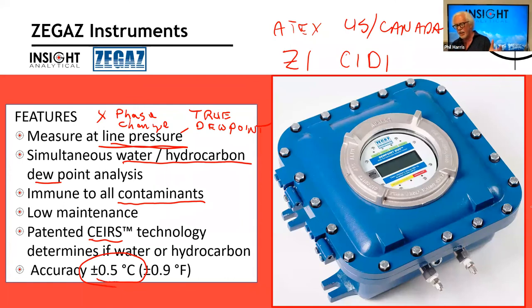Now the analyzer has a cycle too. It's got to cool down the mirror to measure the dew points, and so there's some time delay with that as well. On the analyzer, we'll often see a few minutes of cycle time. Transport time is fairly fast. So you should figure on probably being able to get a reliable update in the order of 5 minutes.